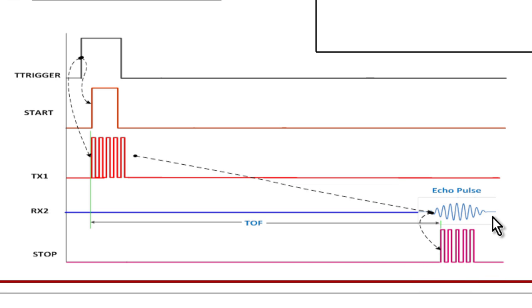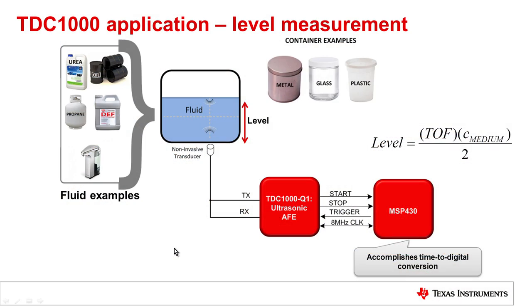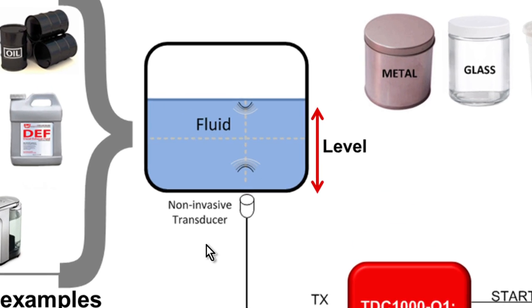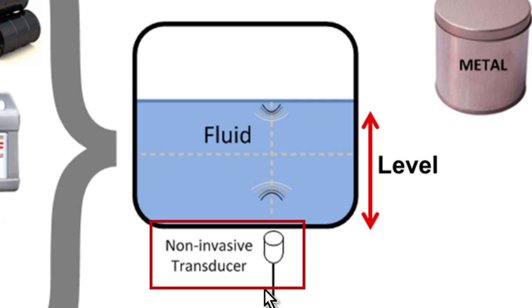Let's talk a little bit about the applications for this. A pulse echo application is best illustrated for level. In this case, I've got a non-invasive transducer mounted outside my container that's inducing energy into my medium, and at that medium-air interface, I'm getting a returning echo.